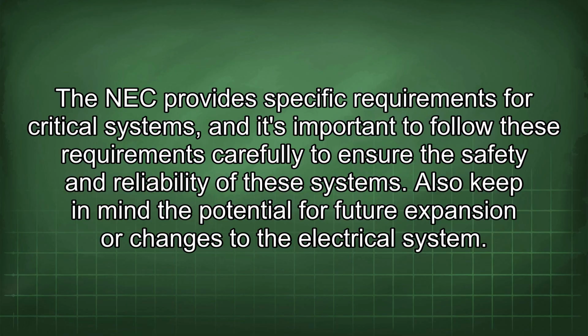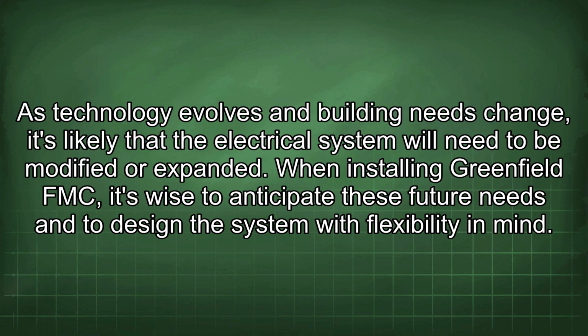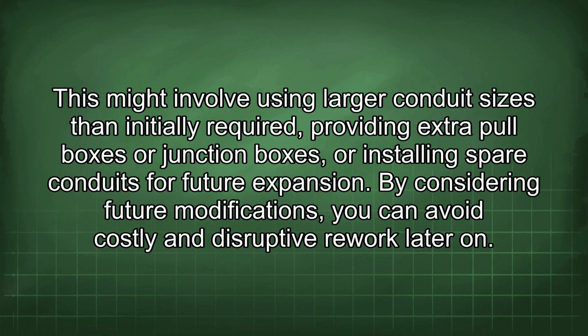Also keep in mind the potential for future expansion or changes to the electrical system. As technology evolves and building needs change, it's likely that the electrical system will need to be modified or expanded. When installing Greenfield FMC, it's wise to anticipate these future needs and to design the system with flexibility in mind. This might involve using larger conduit sizes than initially required, providing extra pull boxes or junction boxes, or installing spare conduits for future expansion. By considering future modifications, you can avoid costly and disruptive rework later on.